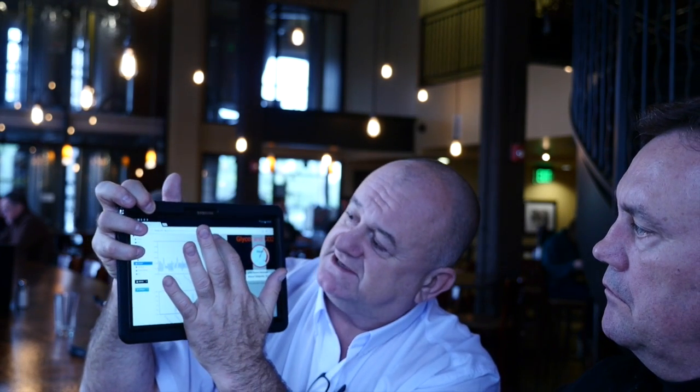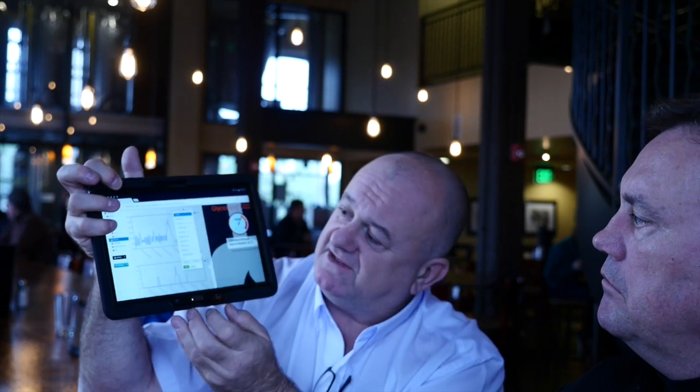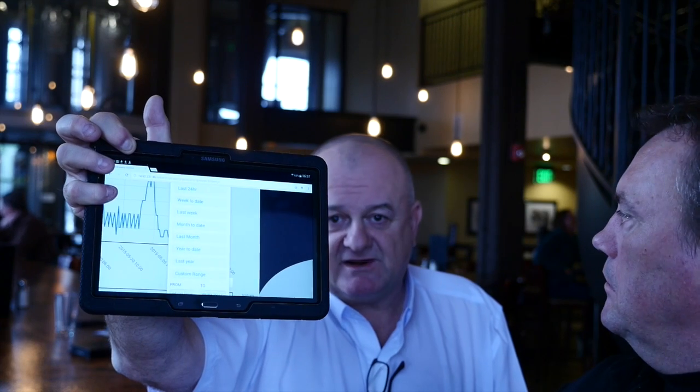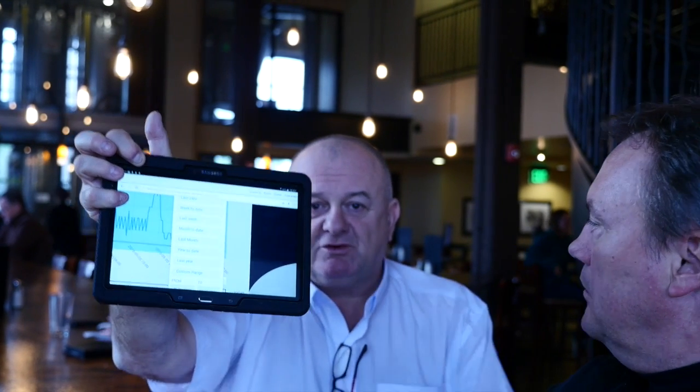If you just tap this little tab here, you get a selection of yesterday, last week, and I'll make it bigger because it is HTML5. There's the choice of menu you get, and that will go to our SQL database on our SD card. So not only do we have a built-in SQL database, we also have HTTP requesting web services. We can have up to 32 columns in one table, so a whole chiller plant, even a whole brewery with one timestamp.